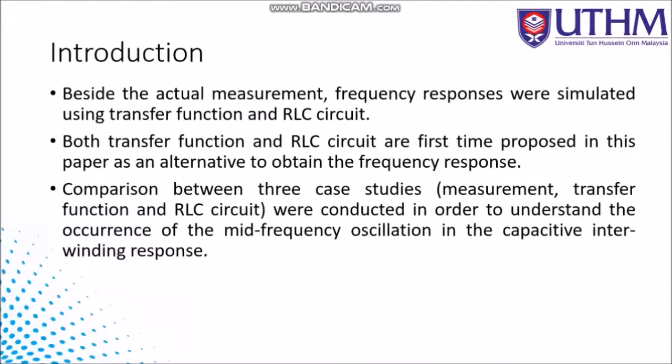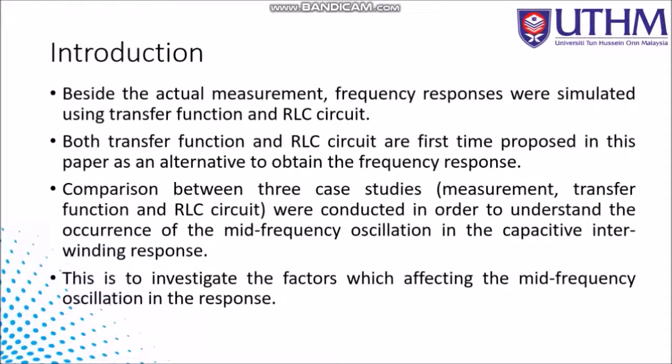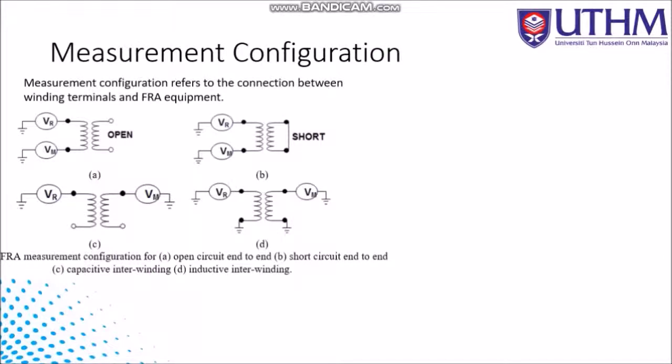A comparison between these three case studies — actual measurement, transfer function, and RLC circuit — was conducted in order to understand the occurrence of the mid-frequency oscillation and the affected part in the capacitive interwinding process. The study's objective is to investigate the factors affecting the mid-frequency oscillation of the response.